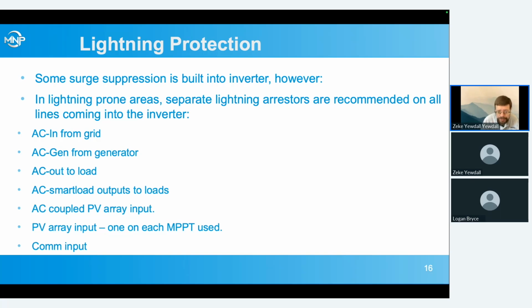Any smart loads, that's also a point where it can get into the inverter. PV arrays, AC coupled or DC coupled, each one needs its lightning protection. And one that people often don't think about is the COM inputs.